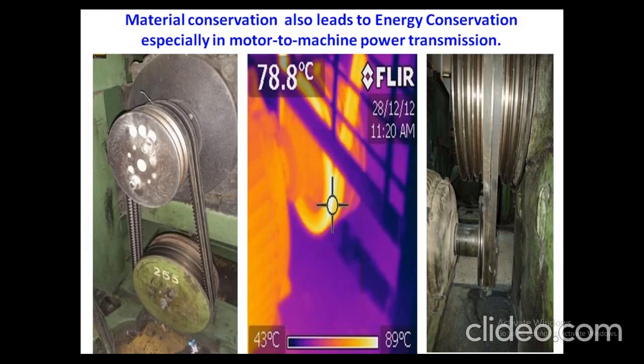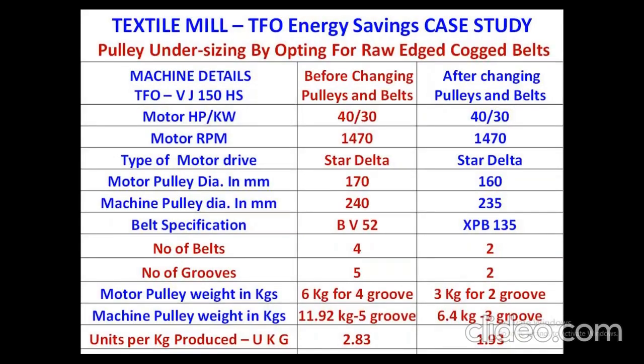Any thermal imager used in the mill, do not use it only on your electrical panel, use it on all the belts also. If the belts are hot by more than 20 or 30 degrees above the ambient, that is a loss to the belt, a loss to the machine, and a loss to the mill as such. We have done an energy audit for one big group. We suggested they go for cogged belts, and we suggested they resize the pulleys.